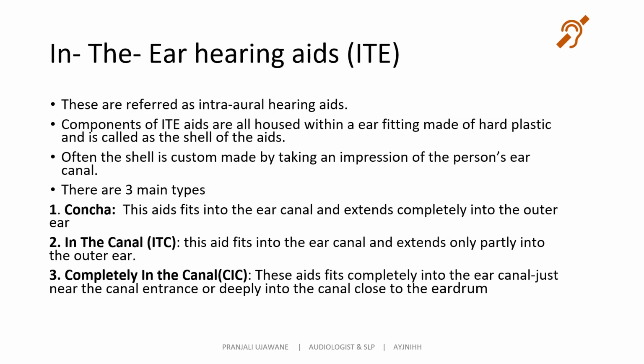ITE hearing aids are referred to as intra-aural hearing aids. The components of the ITE hearing aids are all housed within the ear fitting of hard plastic, called the shell of the aid. Often the shell is custom made by taking an impression of the person's ear canal. There are three main types. Concha: these aids fit into the ear canal and extend completely into the outer ear. In the ITC, that is in the canal, these aids fit into the ear canal and extend only partly into the outer ear. Completely in the canal, that is CIC: these aids fit completely in the ear canal, just near the canal entrance or deeply into the canal, close to the eardrum.